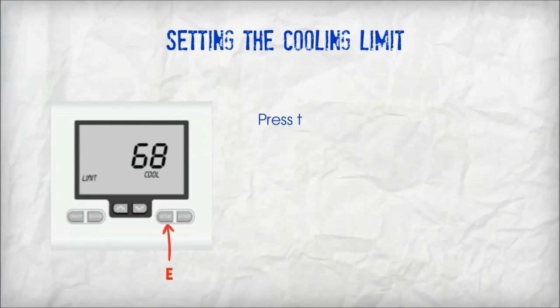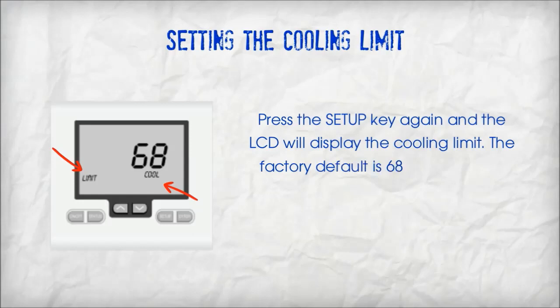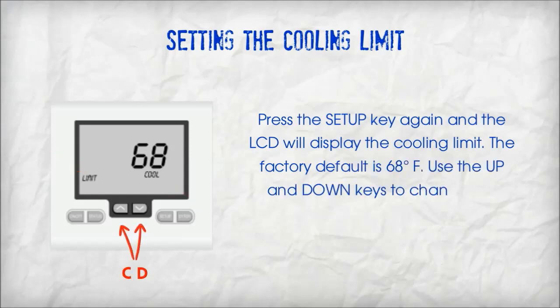Setting the cooling limit. Press the setup key again and the LCD will display the cooling limit. The factory default is 68 degrees Fahrenheit. Use the up and down keys to change the cooling limit setting. If using a zone panel, it is recommended not to go below factory default.